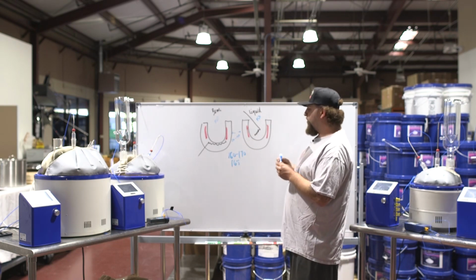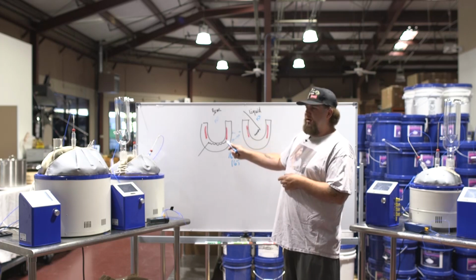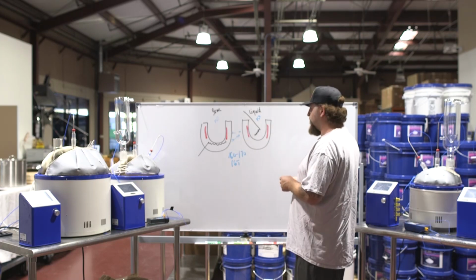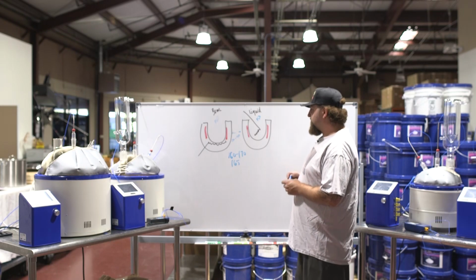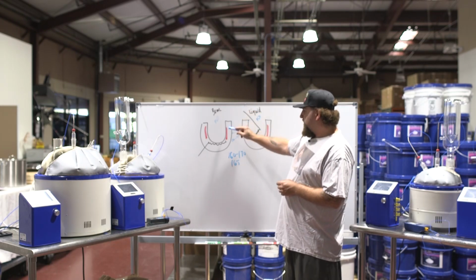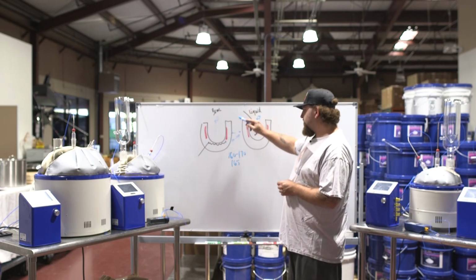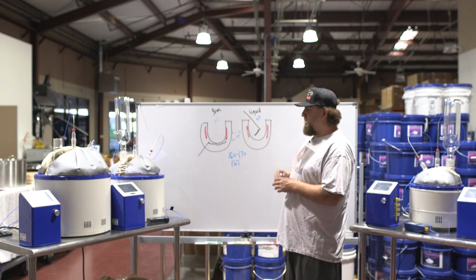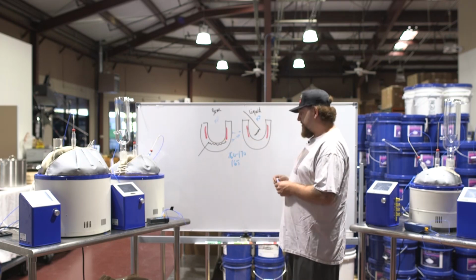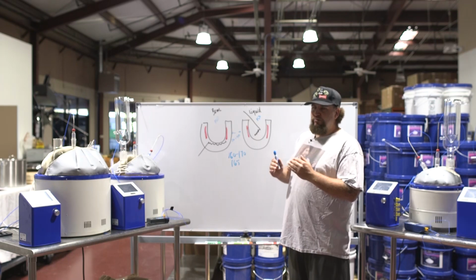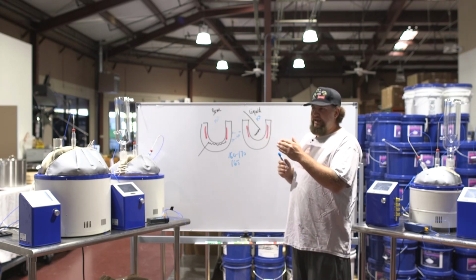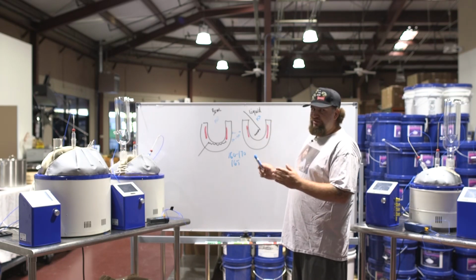And that's how hot the bowl must remain at any given time for the center of the system to see 150. So what happens is, in this case, with the bowl, heat is generated around the entire location, but where it sees the heat is almost instantaneous. So it drives the heat zone right up to where it needs to be at, and then it brings it back down.